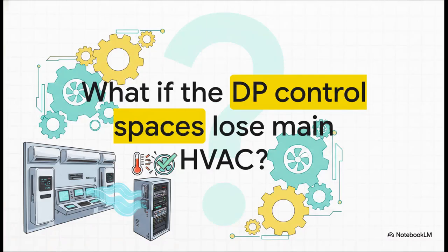Now, what happens to your DP control spaces if the main chilled water HVAC system completely fails? This is a huge vulnerability people miss. We have to guarantee that the independent, packaged air conditioners will auto-start to protect those highly sensitive DP controllers from permanent heat damage.